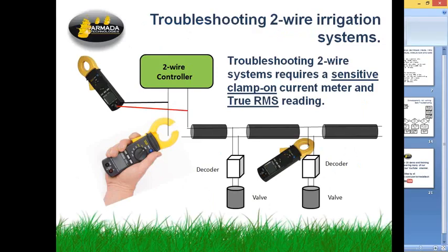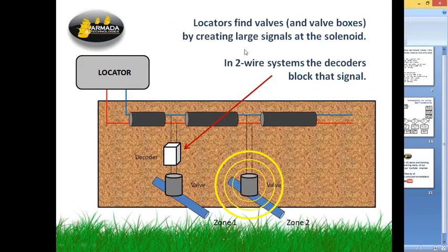It also has a peak hold function, so you can tell it to hold the maximum voltage it sees. That way you can read the real system voltage. Very useful, important things when you're doing this. And as you go into the field, like I said, when you're missing current, or you have too much current, or current's all in one wire instead of the other, you can figure you've got faults to ground out there, you've got cuts in the wire on one side or the other side. So find valve boxes, open them up, and clamp the clamp meter around to see if the currents are what you expect. We talk a little bit about this in our training course. So that's what you end up doing. And this is probably the most important added tool when you're doing this sort of a system.